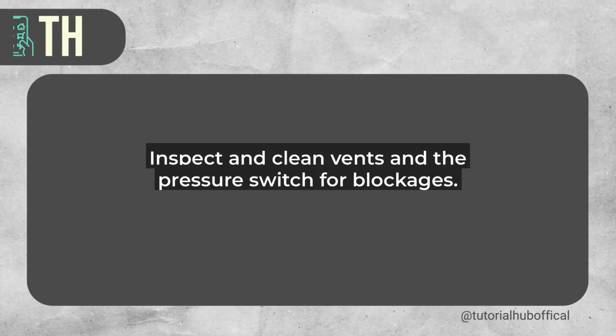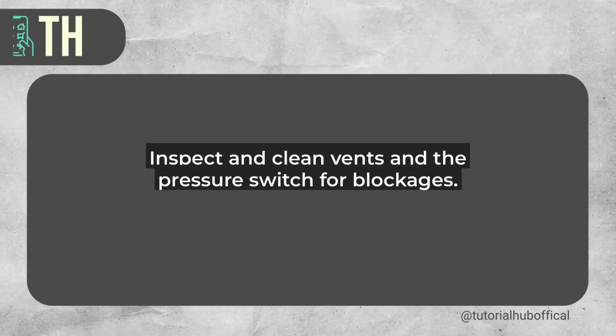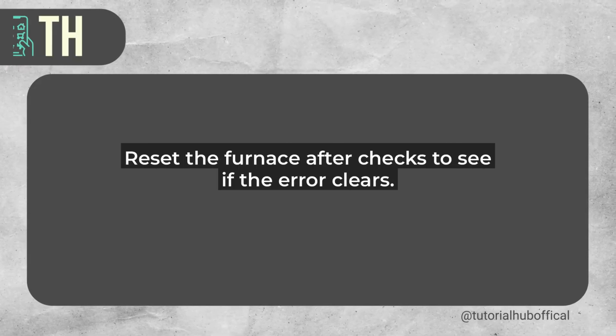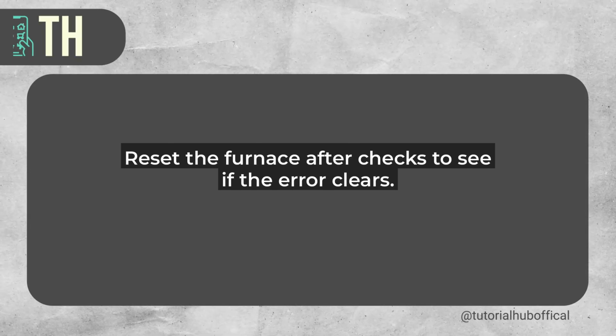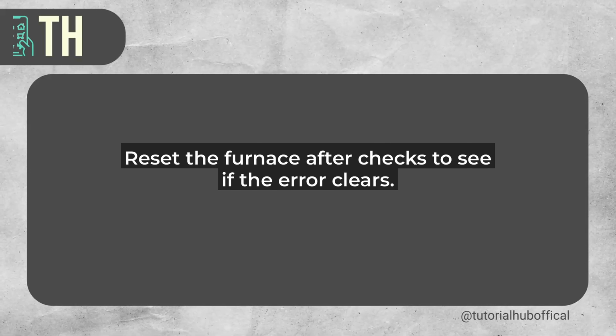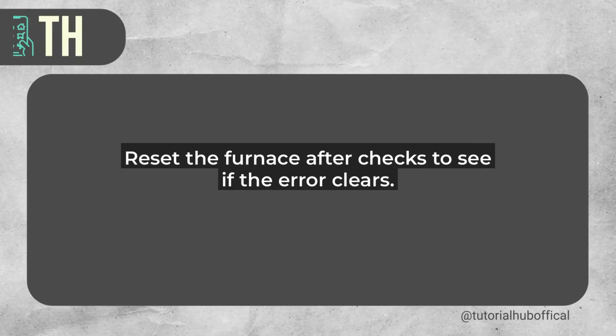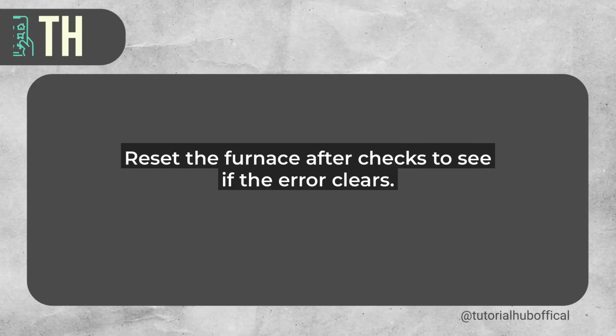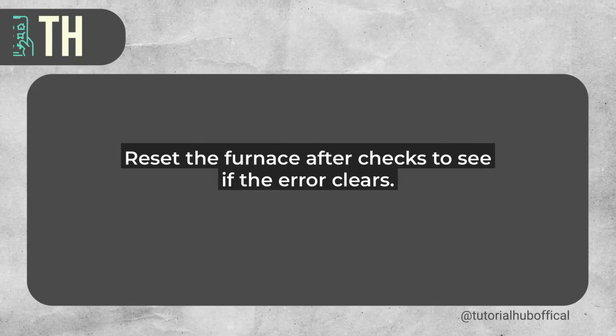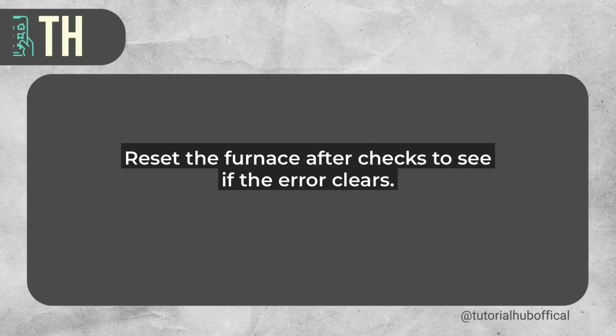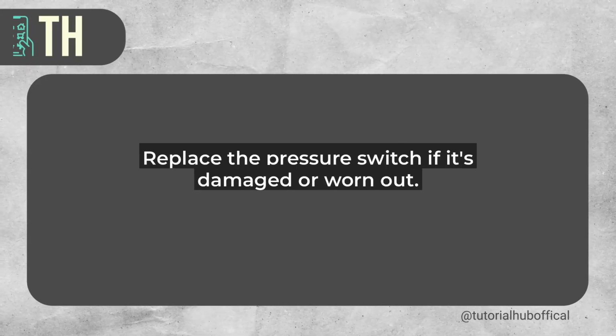Start by turning off the power to your furnace at the circuit breaker for safety. Then, check for any obvious blockages in the vents or exhaust pipes. Make sure nothing's obstructing airflow. Next, inspect the pressure switch. It's usually located near the burner assembly. If it looks dirty, gently clean it with a soft brush or compressed air.